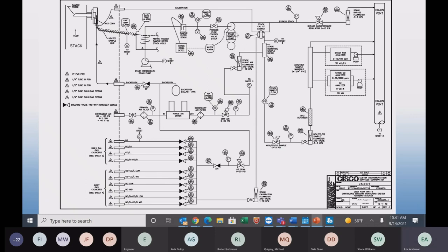Quick check on the pump, the process flow valve, typically mounted on the front panel. If you close that off all the way clockwise, you should be dead ending the pump. So here's your bypass flow meter. The system only has one sample flow meter for these basically three analyzers.